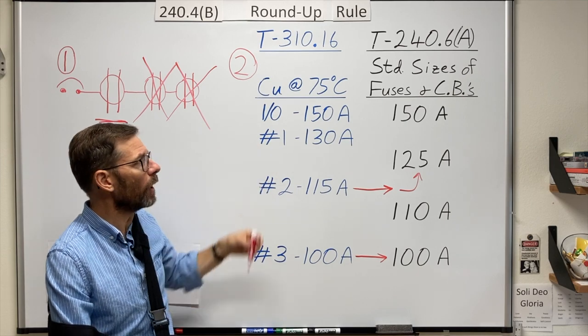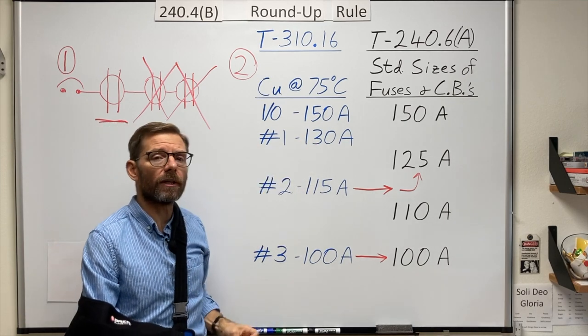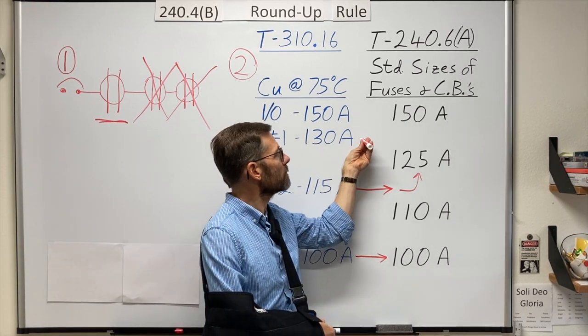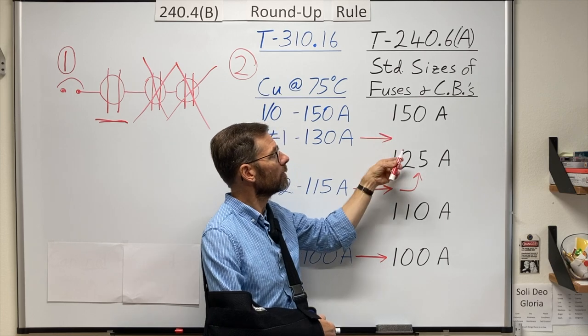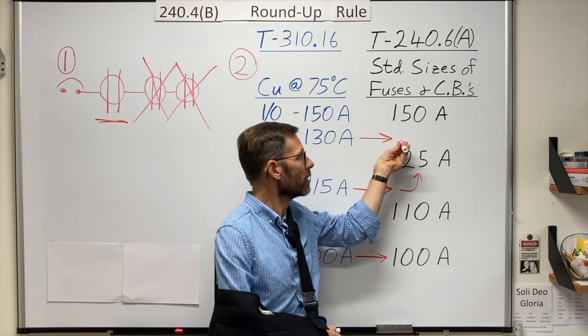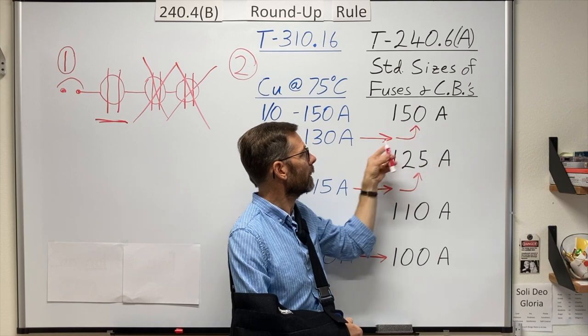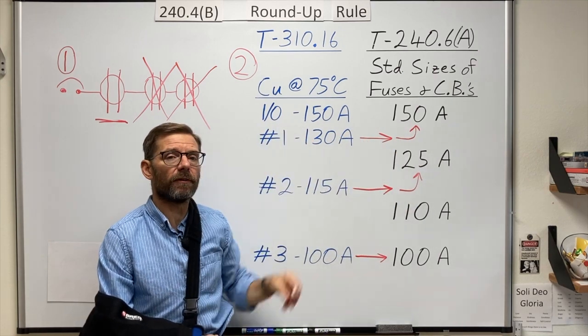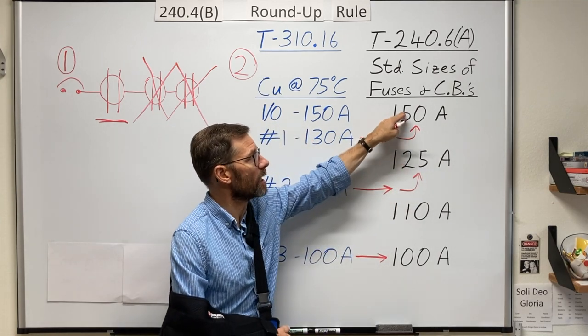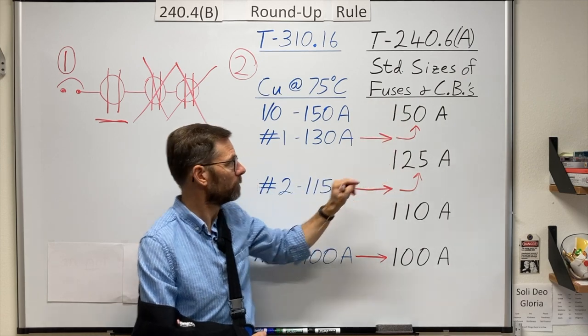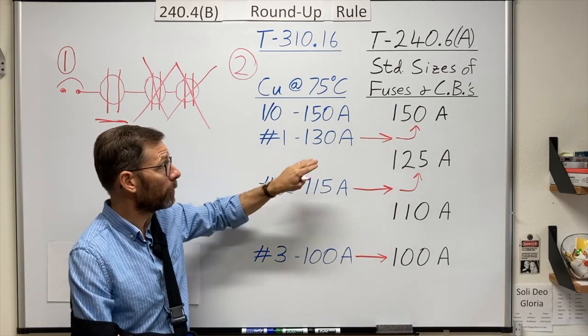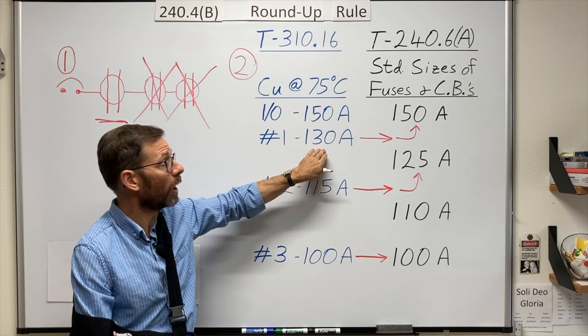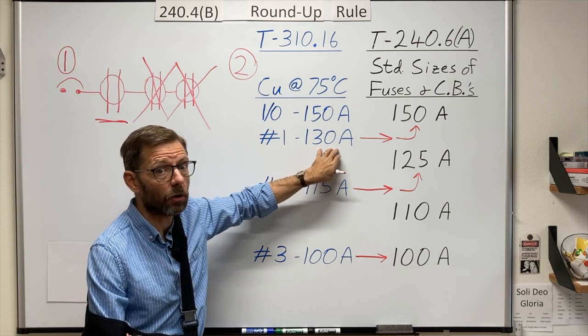So what do you think for the number one conductor rated at 130 amps? Comes in between two standard sizes. So yeah, I can protect this with the 150 amp breaker. There's no standard sizes between these two. But, remember that I cannot put more than 130 amps of calculated load on this conductor.